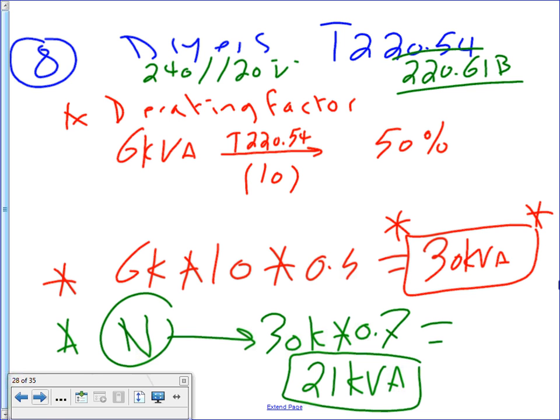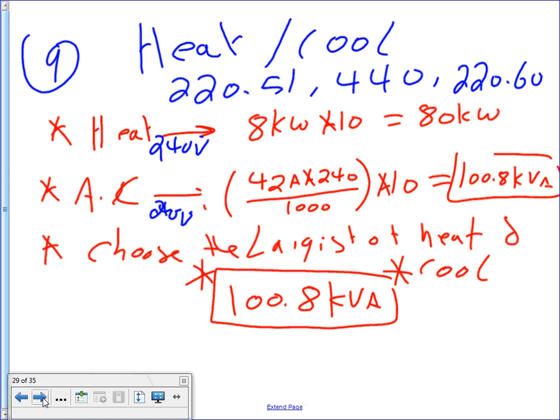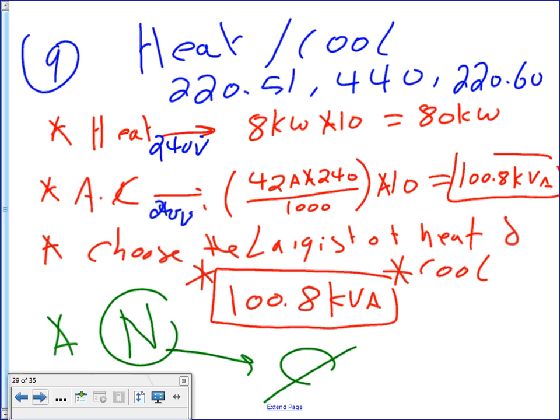Cool. Okay, so now moving into heating and cooling. Now the heaters, they're pure 240. AC, pure 240. When I say pure 240, there is no 120. You send just two hots to them. So this step won't count when it comes to the neutral. If I were you, I would come over here. We're sizing a neutral. What step here? Here's my neutral, and I would say a big fat fluffy 0. Why would I put 0 here, guys? So I know I accounted for them. They don't account for anything. They are 0.